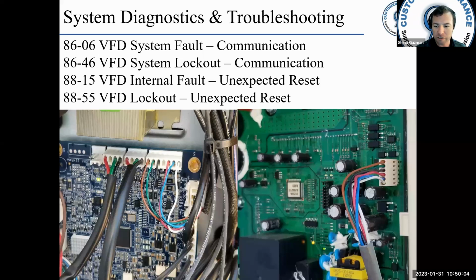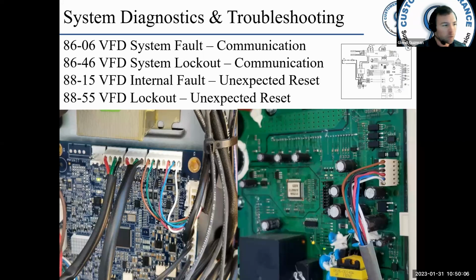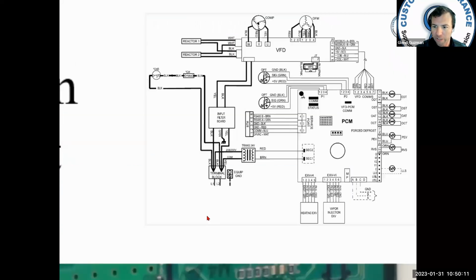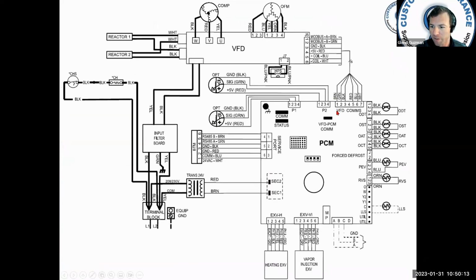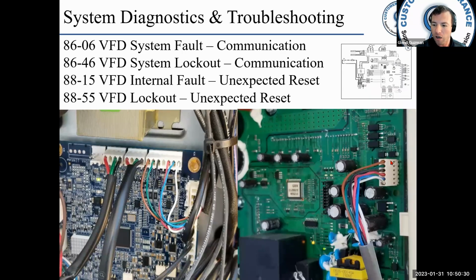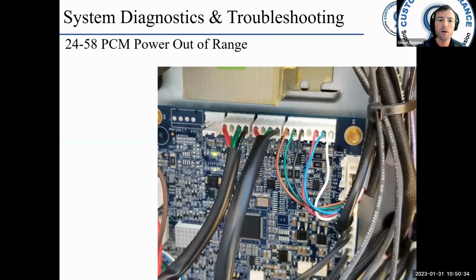What you want to do is look at the wiring diagram. Okay. You can see it here a little bit better. VFD communication, right? VFD comms is a 7-pin plug, okay, only 6 wires, and it goes up to a 6-pin plug on the VFD. So that is the plug that I'm showing you here in this case, on the left and on the right.